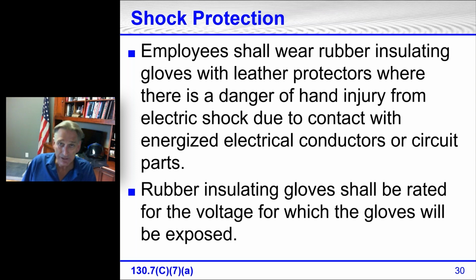Again, this is not everything that's in 70E. We're just doing a very short webinar that Grace is providing for you for free, which is wonderful of Grace to do. Employees shall wear rubber insulating gloves with leather protectors where there's a danger of hand injury from electric shock due to contact with energized electrical conductors or circuit parts.